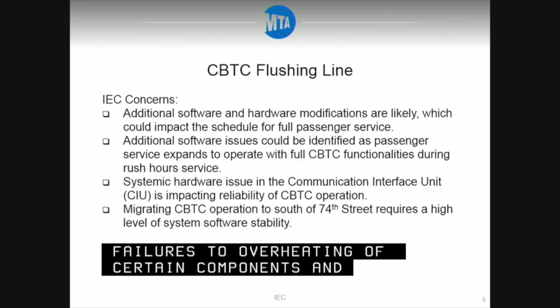Another concern was that during the last 6 months, the CBTC system experienced a high level of hardware failure in the communication interface unit. This has impacted the reliability of CBTC operation. The contractor attributed the failures to overheating of certain components and plans to use cooling fans to resolve this issue. The IEC is concerned that retrofitting all CIU elements with fans could impact the project schedule.